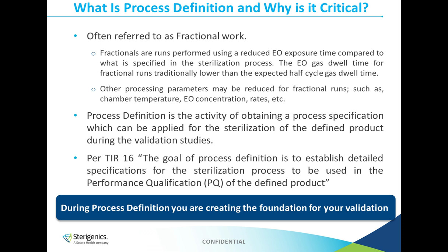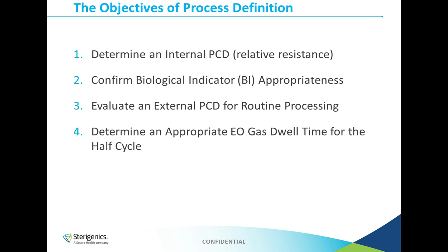In order to have a solid validation, you have to have a good base, and this is your process definition work. Now, some of the objectives we're going to look at during process definition are: we're going to determine your internal process challenge device, or PCD, through relative resistance. We're going to confirm BI appropriateness. We're going to evaluate an external PCD, and we're going to determine an appropriate EO gas dwell time for your half cycle. Now, I'll go into more detail about each of these in the coming slides.